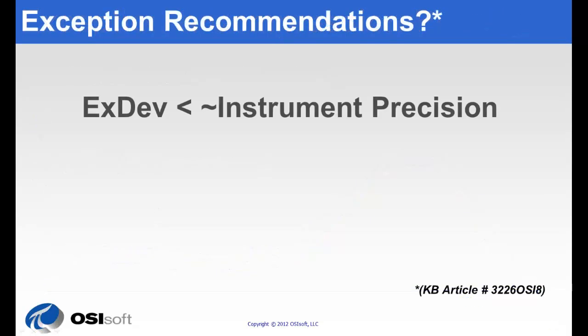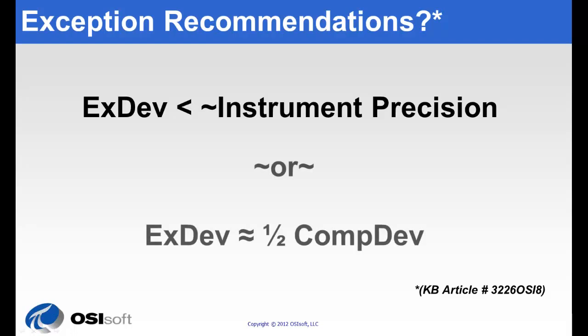Exception settings should generally be slightly less than the instrument precision, or you can set it to be about half of the compression deviation. For more details, you can consult this KB article on our website, 3226-OSI-8.